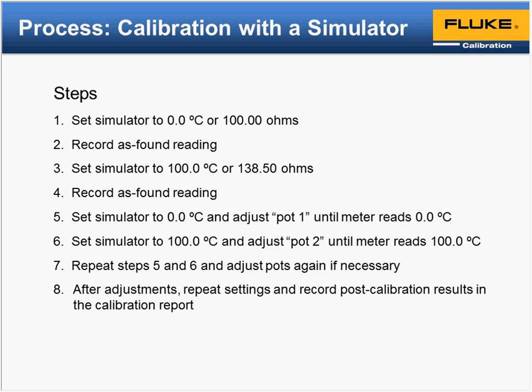So now we've established where we're at. Now we're going to go back and simulate 0 and make any adjustments needed to that first trim pot until we read right at 0. Then we repeat the process and go to 100 degrees C and adjust the pot until it reads properly there. You may see a linearity issue, where you adjust one pot up and it pulls your bottom reading down. Sometimes you may have to repeat steps a couple of times to limit the top down slightly, or you'll see a slightly high top end, and then it pulls 0 in right where you need it to be. We'll discuss that a little bit further.